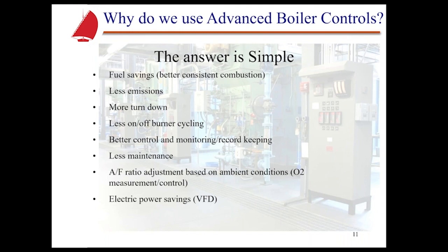And as I mentioned earlier, these types of systems will allow us to do more turn down. And that really gives us a lot more flexibility because we're going to have less on and off burner cycling. So there's our efficiency gain right there. We can actually turn it down and it's ready to go. That also gives us a lot quicker response too. So if it's sitting at low fire and that's sufficient, if the load changes, it can respond much quicker than actually having to go through a start sequence where we have purge, pilot trial for ignition, main trial for ignition before we actually are able to catch the load. So there's a huge advantage there.